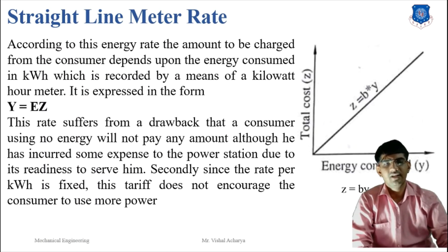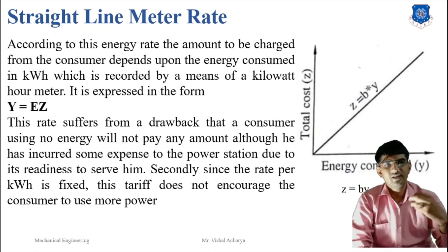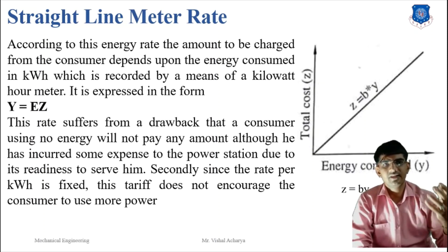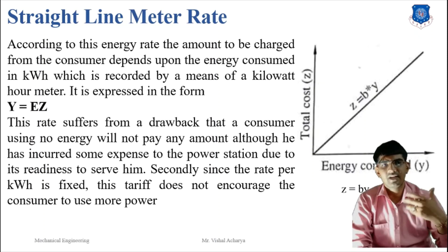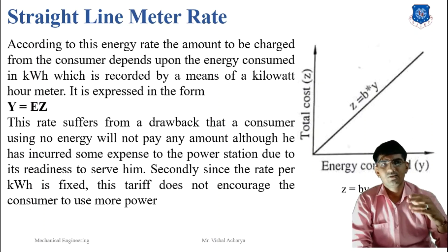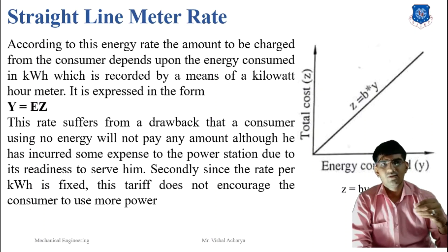Next is the straight line meter rate. According to this rate, the amount to be charged from the consumer depends upon the energy consumed in kilowatt-hours, recorded by means of a kilowatt-hour meter. The cost increases as energy consumption increases. A drawback is that a consumer using no energy will pay nothing, yet the power station still incurs expenses due to readiness to serve. The rate per kilowatt-hour is fixed, so the tariff does not encourage consumers to use more power.